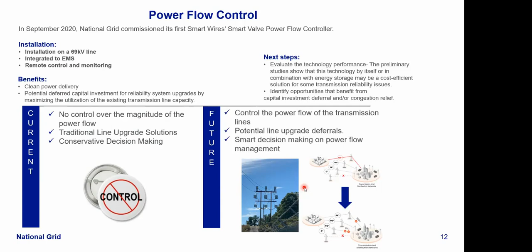To conclude this presentation, I strongly recommend that utilities and ISOs take a deeper look at grid enhancing technologies. There are a lot of benefits sitting there. DLR and power flow control technologies are tools in the toolbox for some of the system operational and congestion relief issues. I'm also very interested in the future to see DLR and the power flow controller merge together. DLR gives us the rating of the line, and the power flow controller manages the power flow of that line, so that they both work together.